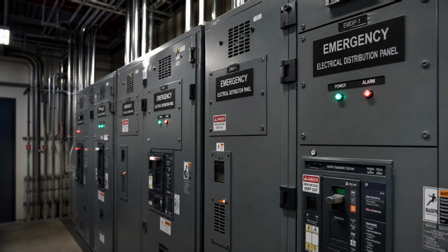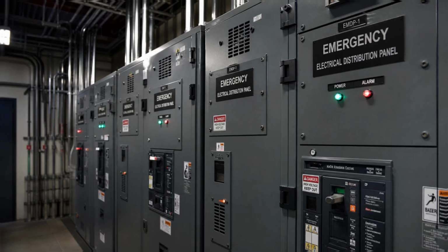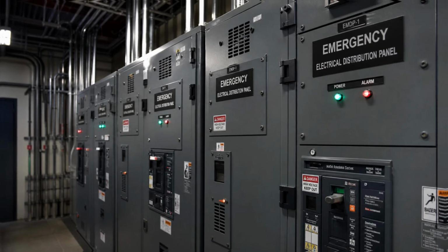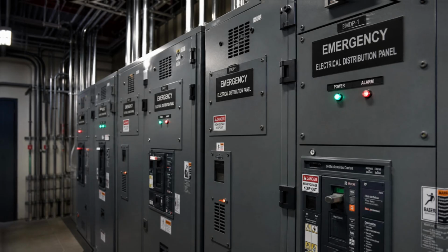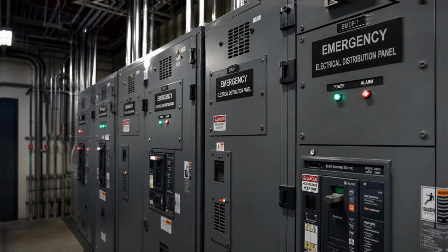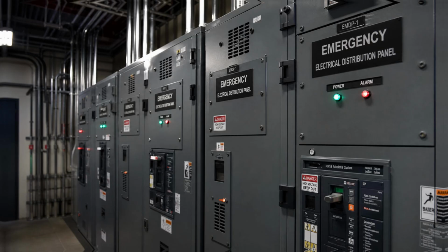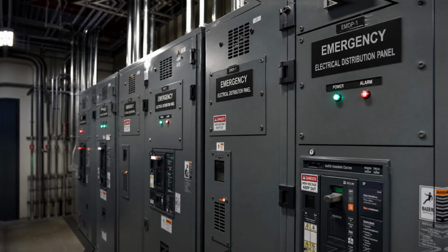The battery receives its own careful attention. The generator starter battery, that lead-acid cell that powers the starter motor and provides the initial energy for the start sequence, is checked for its state of charge, for the condition of its terminals, for any sign of swelling or distortion or leakage that would indicate it is aging poorly or being charged incorrectly. The charger that keeps it at full capacity is verified to be operating. The connections are checked for tightness and for corrosion.